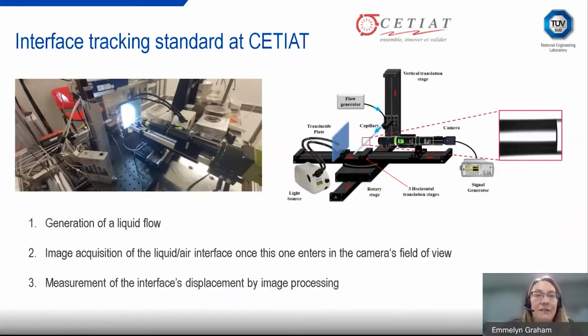Another technique is interface tracking. The images I'm showing here are from CETIAT in France. You can have a glass capillary and actually image the movement of the interface between the water and the air, and then calculate the velocity change and relate that back to the flow rate. In the image on the left, we can see we've got various setups. We've got a syringe pump, a high resolution camera, different optics. We also have a translation stage, so we can move the equipment to get better imaging and to actually track the movement of the interface. On the right hand side, you can see in more detail from the diagram the actual setup of this.